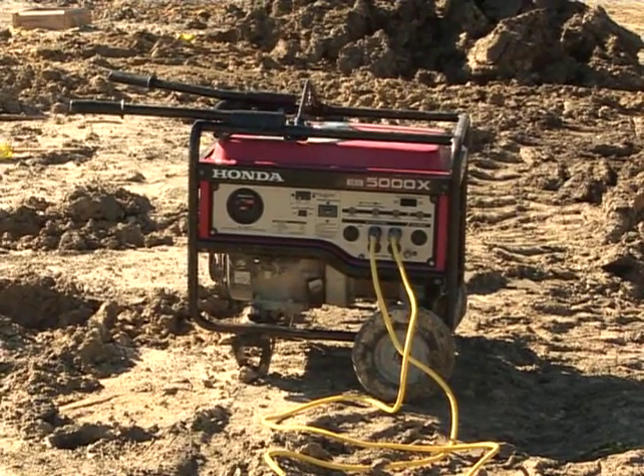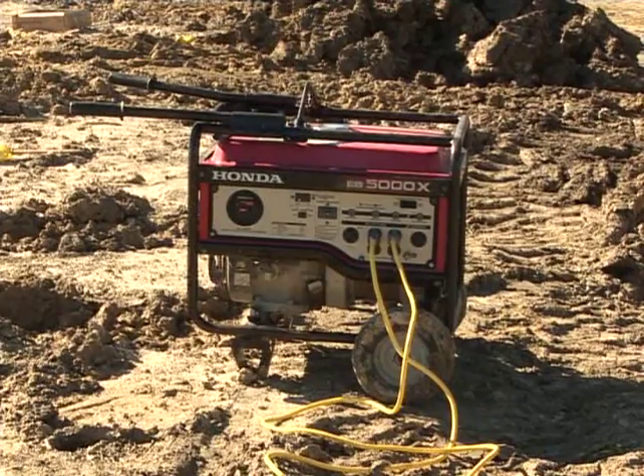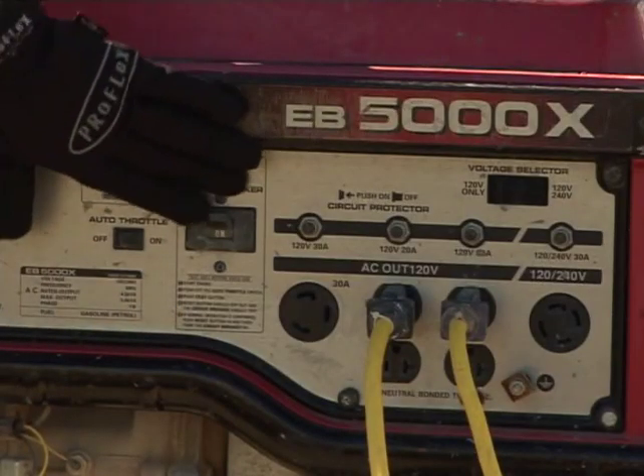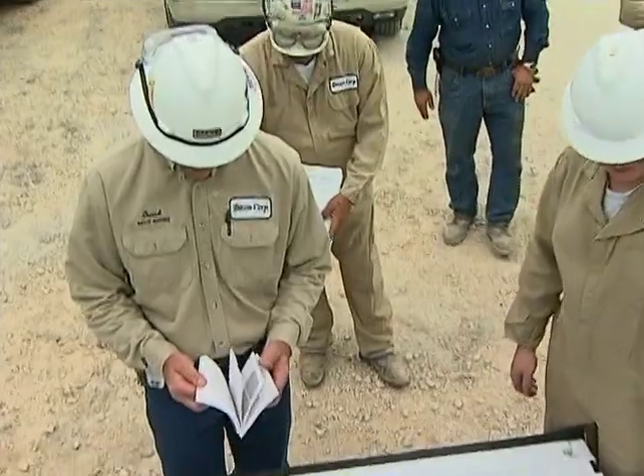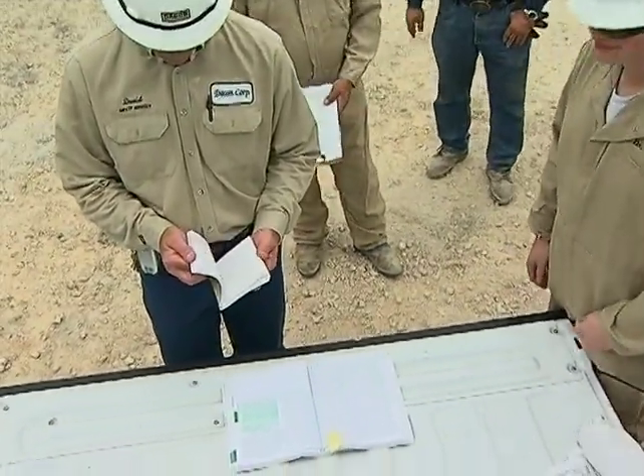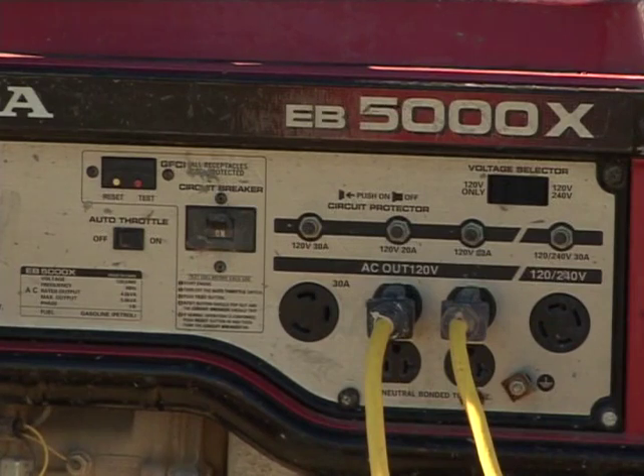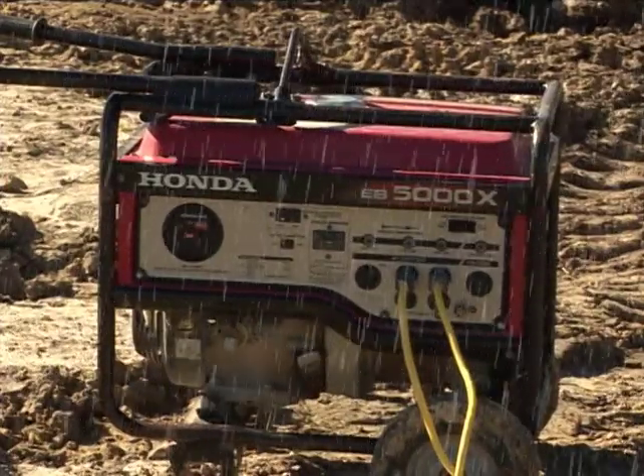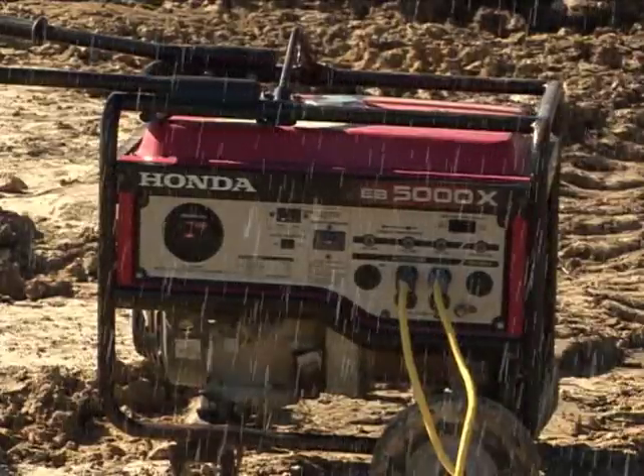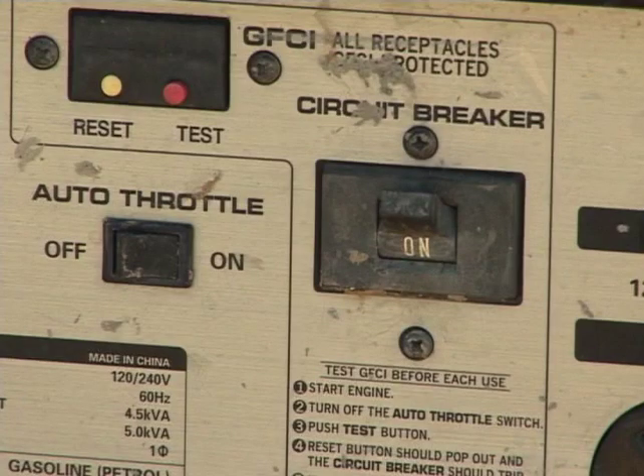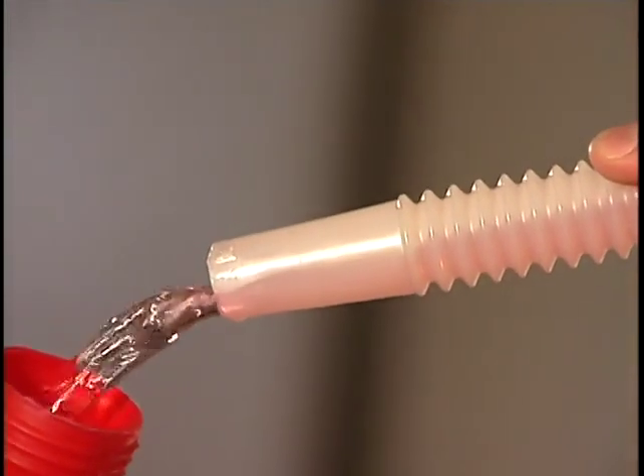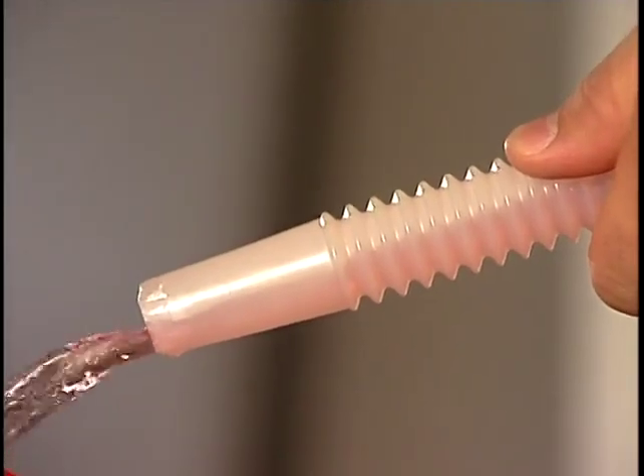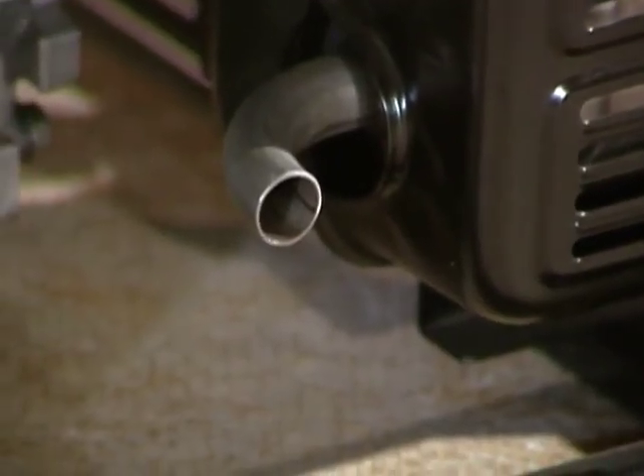Portable generators can also be very dangerous if used incorrectly. Always follow manufacturer's safety rules and guidelines. Read the instruction manual prior to use. Inspect generators before each use. Do not use generators if they are wet or it is raining or snowing. Use only undamaged heavy-duty cords that are grounded as required. Use GFCIs according to manufacturer's guidelines. Shut down and let it cool down before refueling. Never use a generator indoors.